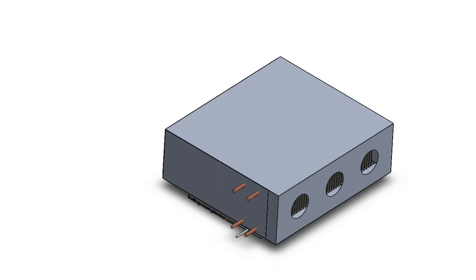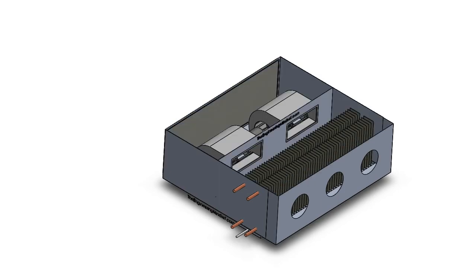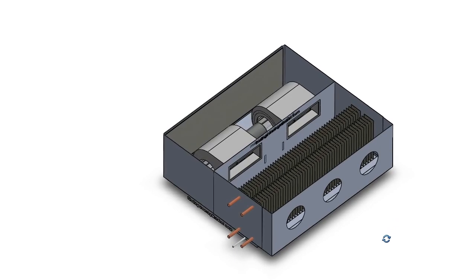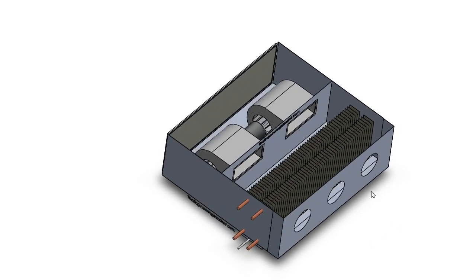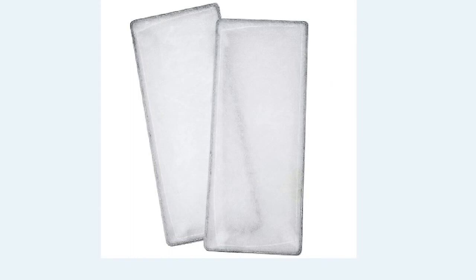Let's have a look inside a fan coil unit. If we remove the lid we can see it's actually fairly simple in design. The air enters through the inlet face where there's a removable filter. Filters can be pulled off or slid out, cleaned or replaced. They're there to stop dust coming in before the air is sent out through the local ductwork around the office.